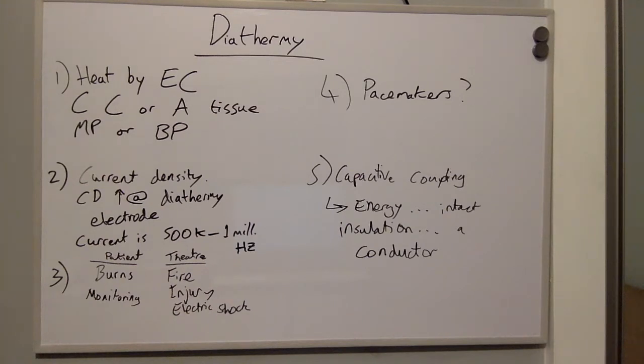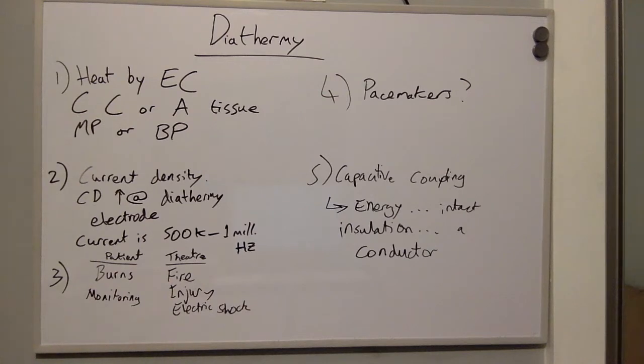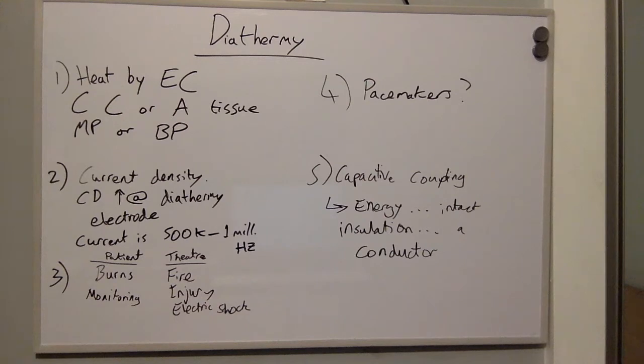The two modes of diathermy include monopolar or bipolar diathermy. How does diathermy cause coagulation? Diathermy causes coagulation by use of an electrical current generating heat, on the principle that there is a high current density at the tip of the diathermy electrode. The electrical current used in diathermy is in the region of half a million to one million hertz.